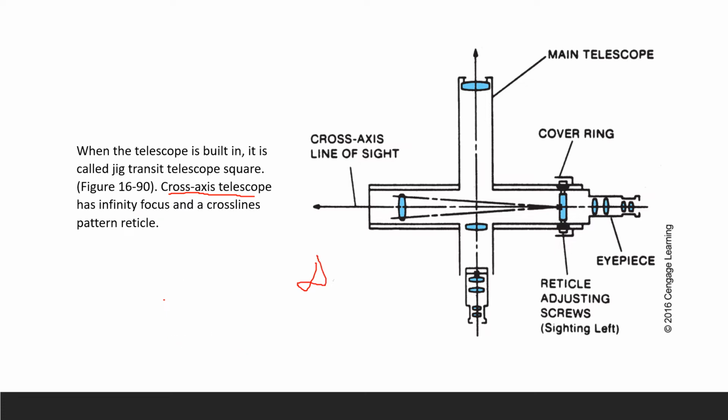Alright, so when you look at this picture, so let me clear this out of my mess here. Okay, here we go. I always forget this laser pointer. So when you look at it here, the two lines of sight here and then here, okay, they intersect. But they do not optically interact. So interaction and intersection, the lines are intersecting. So these are all just imaginary lines, while your instrument is built along these lines, okay, so that you can get your alignment totally correct. And however, optically they're not interacting with each other.